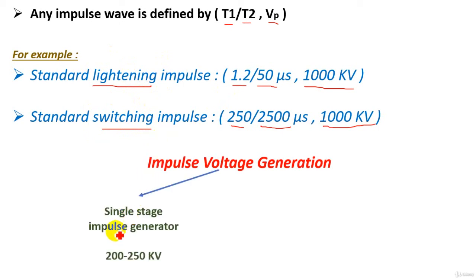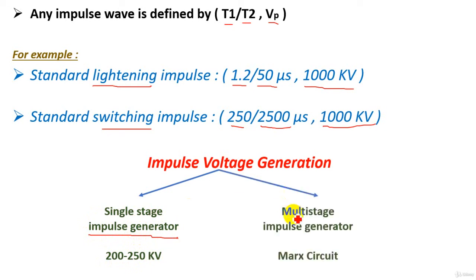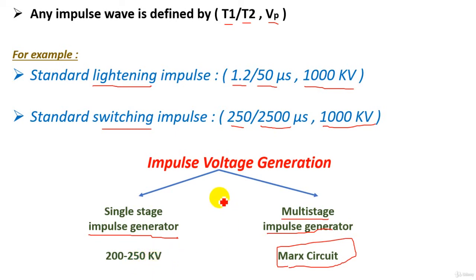Impulse voltage can be generated by two methods. The first is the single-stage impulse generator, which can produce voltages between 200 and 250 kilovolts. For higher voltages, we use the multi-stage impulse generator, also called the Marx circuit, which can produce voltages higher than 250 kilovolts. In the next two lectures, we will cover both methods for producing impulse high voltage.